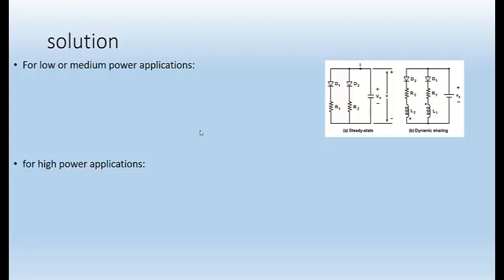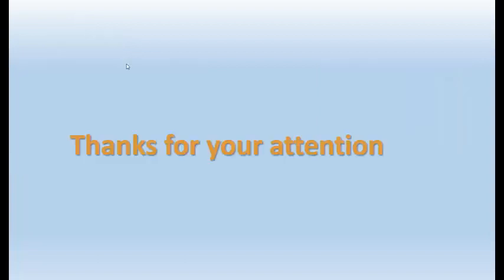In low power applications, we can use suitable series resistors or a combination of resistors and inductors to control current values of each leg. However, for high power applications, the recommended layout is the one with the minimum number of matched diodes, or use diodes with a higher current rating instead of connecting multiple diodes in parallel.